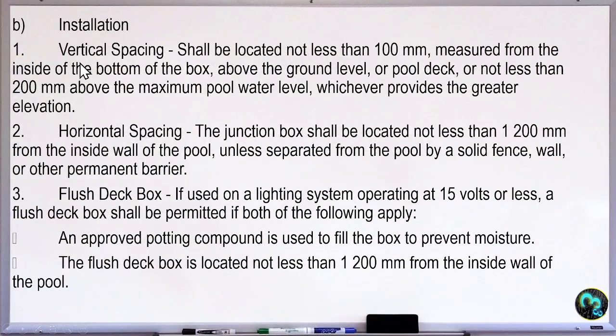The installation to the vertical spacing shall not be less than 100 mm, no? Measured from the inside bottom of the box above the ground level or pool deck or not less than 200 mm above the maximum pool water level, so which provides the greater elevation. The horizontal spacing, so that is the junction box shall be located not less than 1,200 mm from inside the wall pool unless separated by a fence, wall, or permanent barrier.